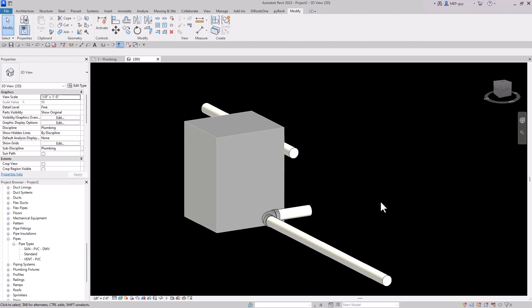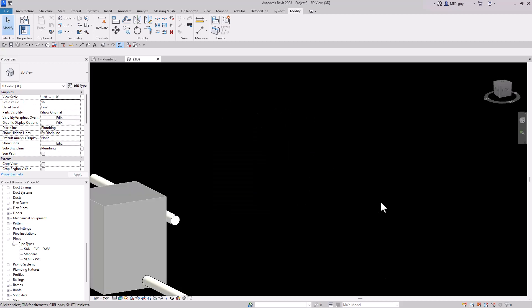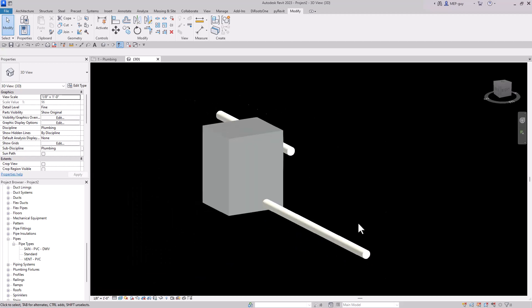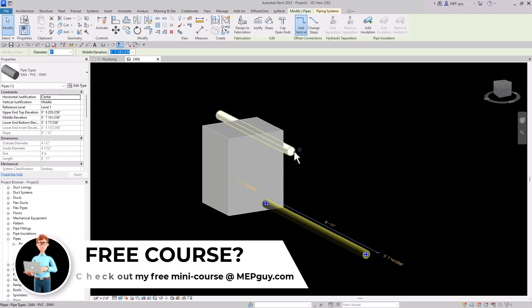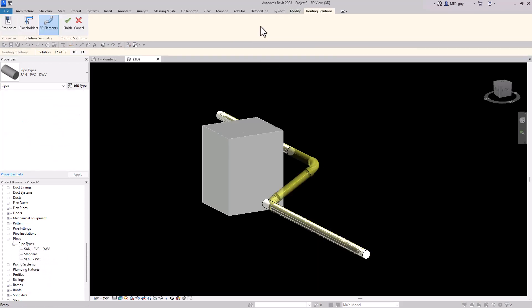I'm going to undo that with Control Z and show you another way — an automatic routing method. I'm going to select this piece of pipe, hold Control and select this other piece of pipe, and now you can see an option called 'Routing Solutions.' If I click it, Revit will come up with some routing solutions for me, which is really nice.